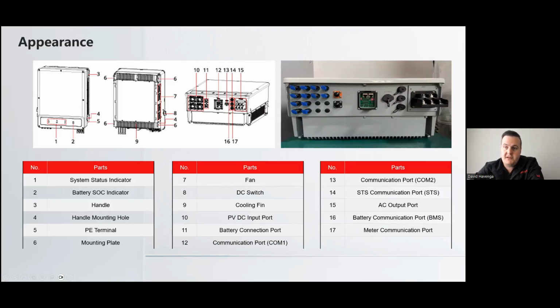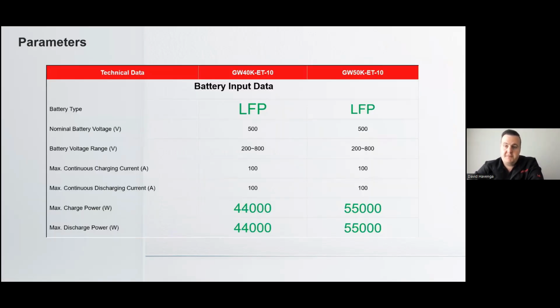And you'll notice one singular AC connection port on the device. So looking at some of the data, we only support lithium batteries, so it is high voltage batteries only, and only batteries in our supported list will work with these devices. We have a nominal battery voltage of 500 volts, with a range from 200 to 800 volts, limited to 100 amps. That's why, in order to get the full capacity of the device, we do need a higher voltage on the batteries, thus the nominal 500 volts.